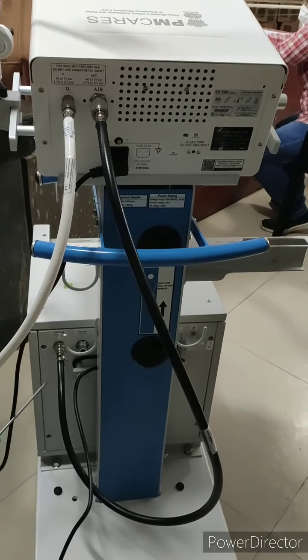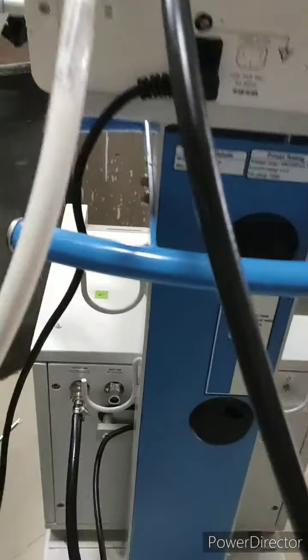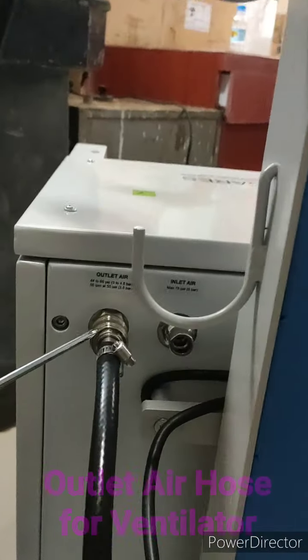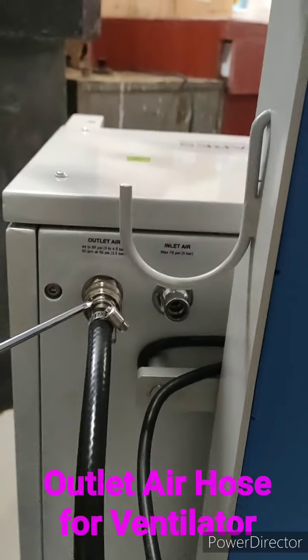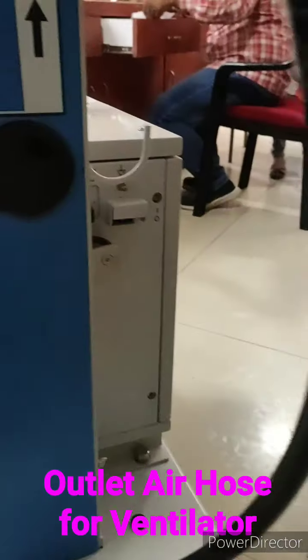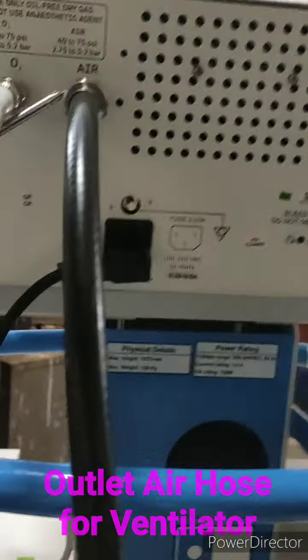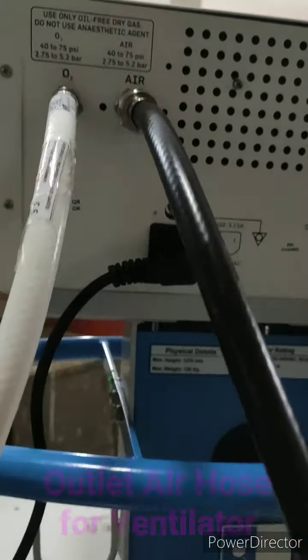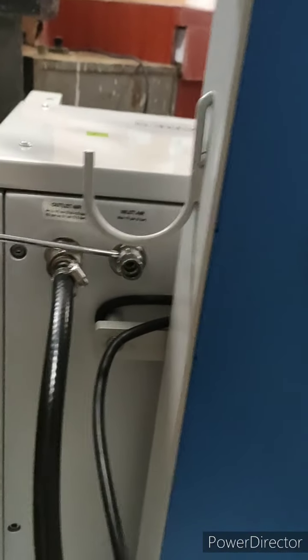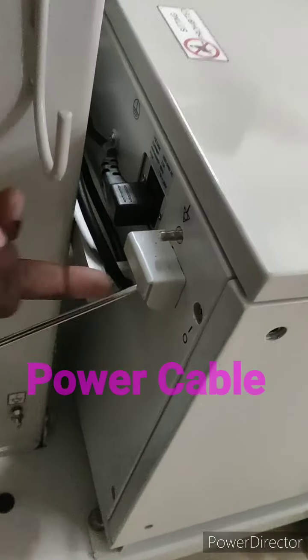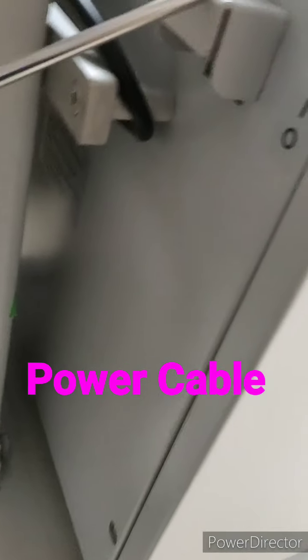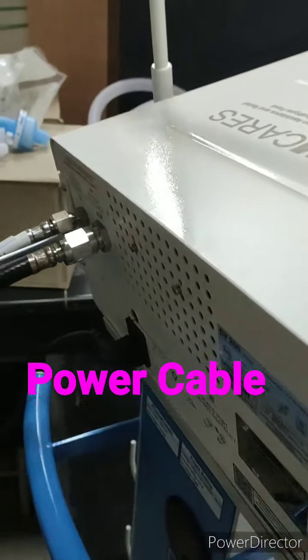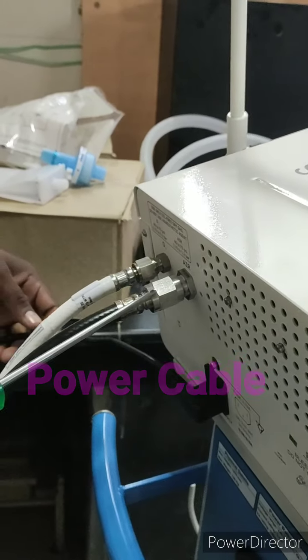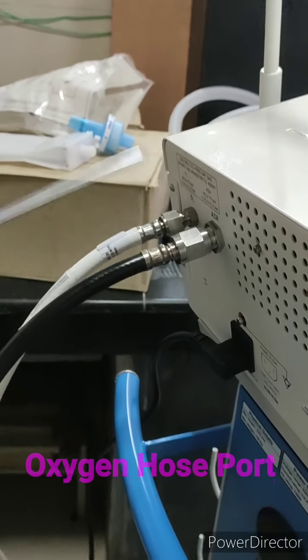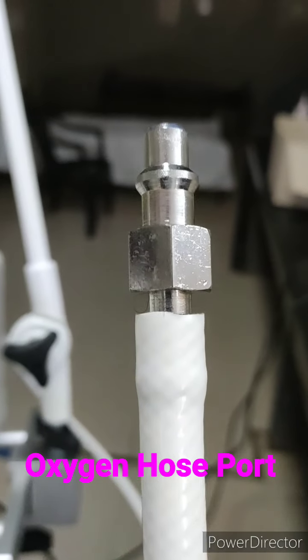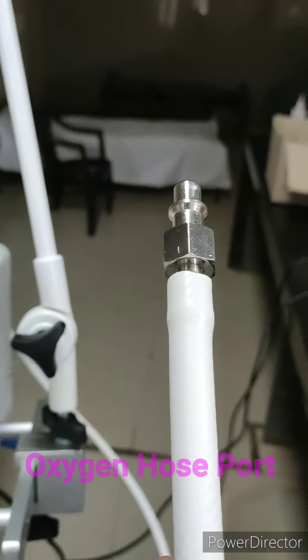This is how CV200 ventilator will look from the back side, and these are the connections. This is outlet air hose which goes to the ventilator, and the other port is empty. The compressor power cable, and here is the on off switch. This is air hose pipe. This is oxygen hose pipe. This is the central oxygen port which will go to the oxygen port.